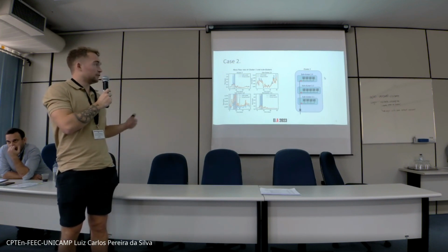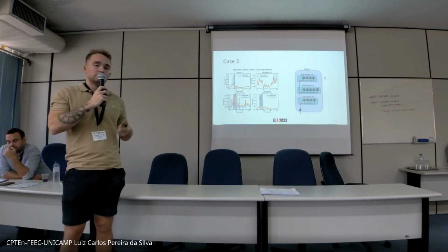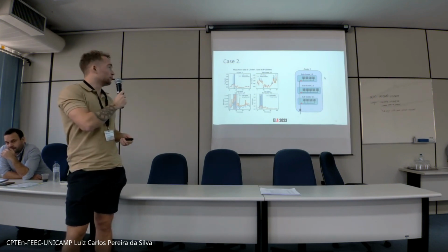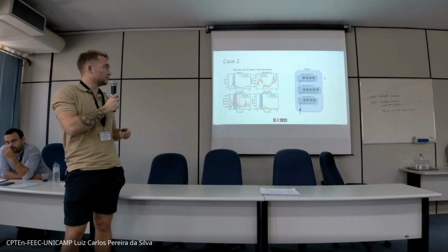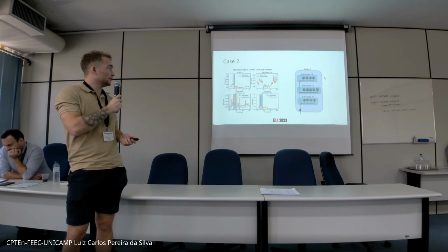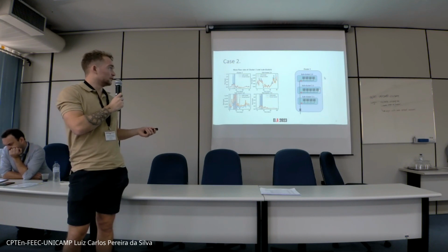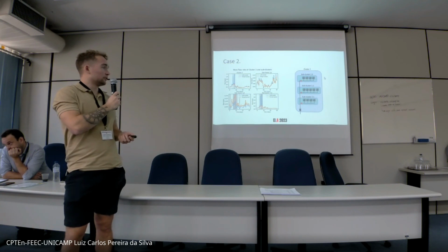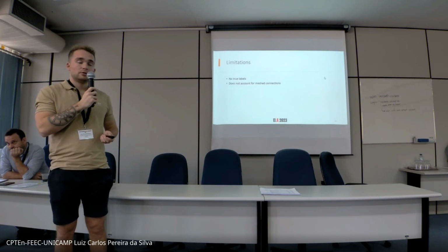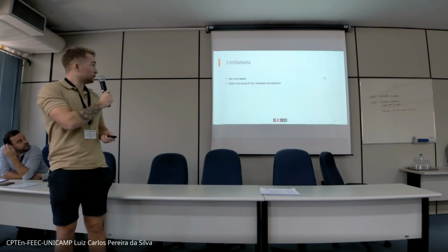Aside from narrowing down the location of the abnormal operation, we also get some indications of what the potential problems could be. It could be a poorly insulated pipe, a burst pipe, or something that is upstream from this cluster. Whereas if we only have a cluster with a single consumer experiencing some abnormal behavior, then the problem is very likely local.